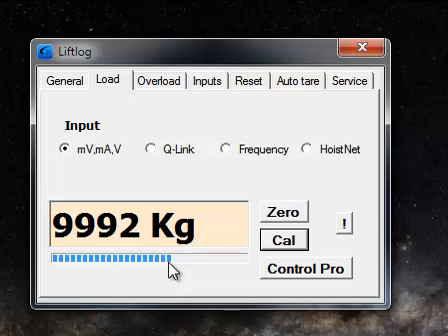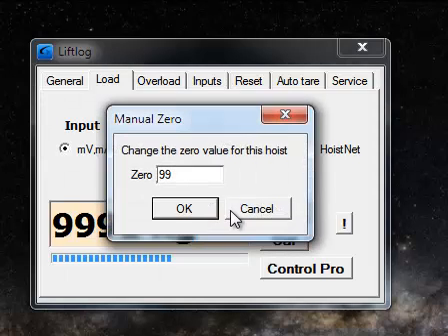But having said that, you can do the same thing with the zero value. So if, with no load on the hook, it's reading just a few kilos over, then you can increase this number. And if it's reading a few kilos under, then you can decrease this number.